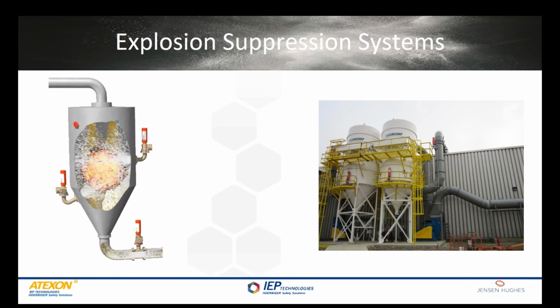The explosion suppression systems take advantage of this gap between the pressure front and the flame front by detecting that pressure very, very quickly, suppressing the fireball. And typically, the time from when an explosion begins, while it's being detected, the extinguishers discharge, and the suppression is completely finished, is something between 70 and 130 milliseconds, depending on the application.